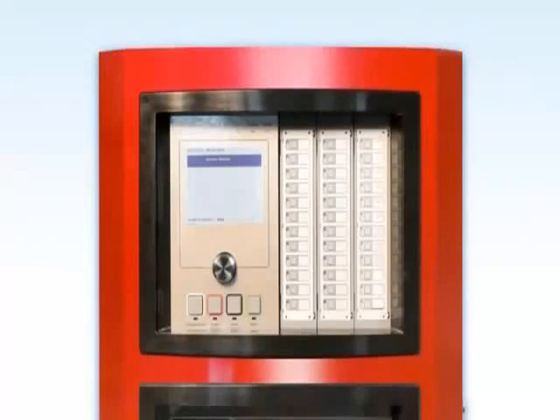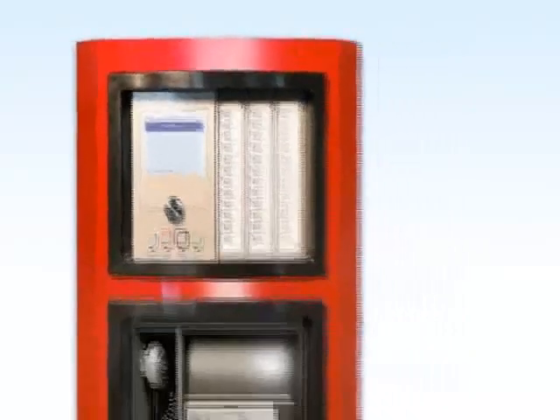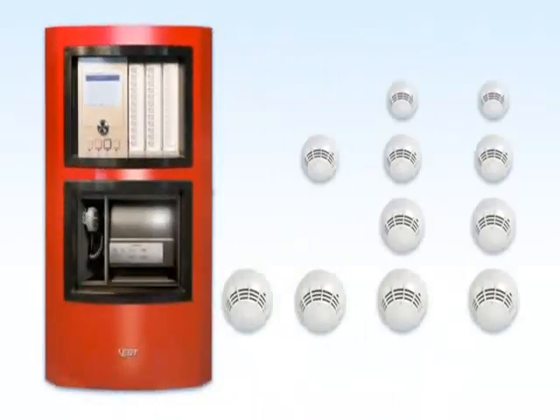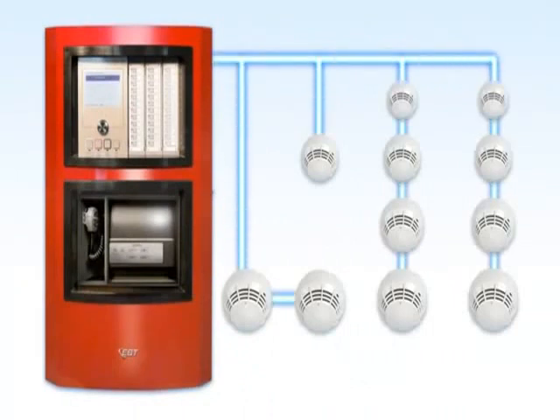The control system's user-friendly maintenance program shows the current state of each CO detector and other pertinent messages. Individual CO detectors may be turned off temporarily from the control panel or placed in maintenance mode for testing. When the CO sensor's electrochemical cell reaches its end of life, approximately 6 years, the detector signals a trouble condition to the control panel. The low-cost single-sensor daughter board is field replaceable, resulting in the most cost-effective solution currently available in the industry.